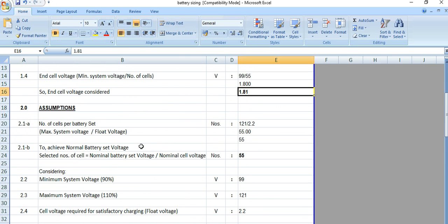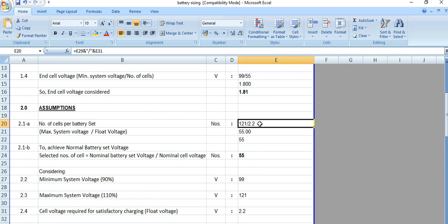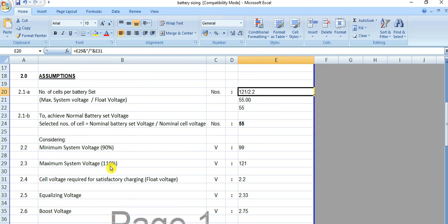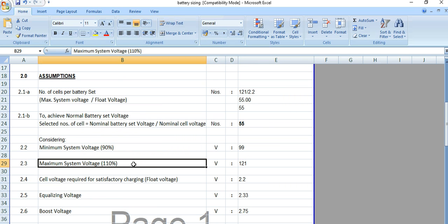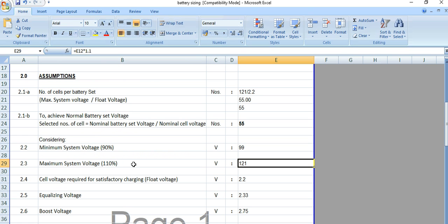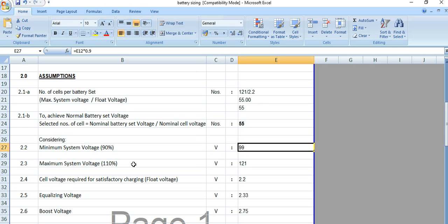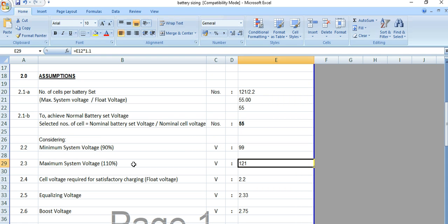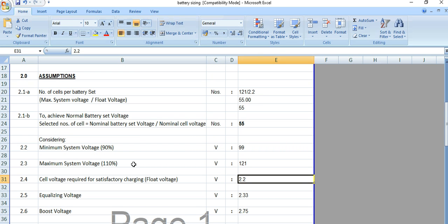For the assumptions to start the battery sizing calculation: the number of cells per battery set is 55, calculated as 121 divided by 2.2, which comes from E29 divided by E31. E29 is the maximum system voltage — 110% of 110 volts equals 121 volts. The minimum system voltage is 90% of 110 volts, giving 99 volts. Float voltage is 2.2 volts.